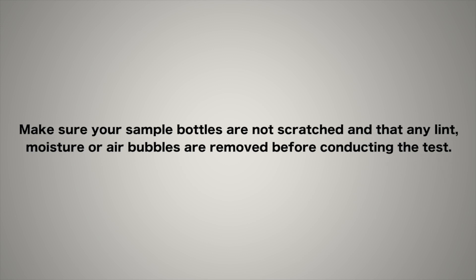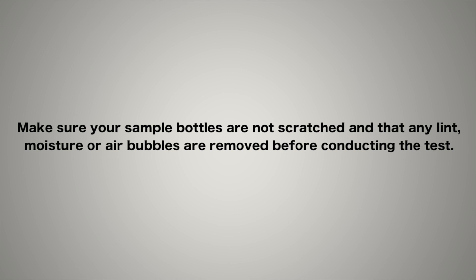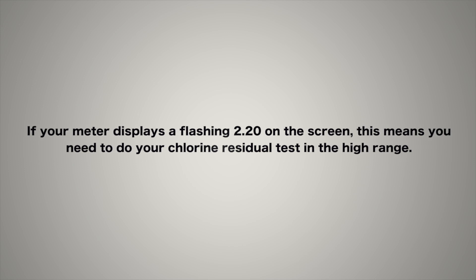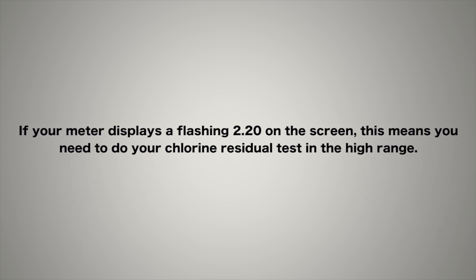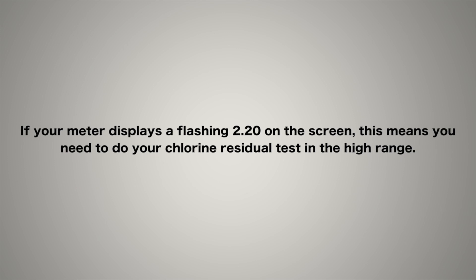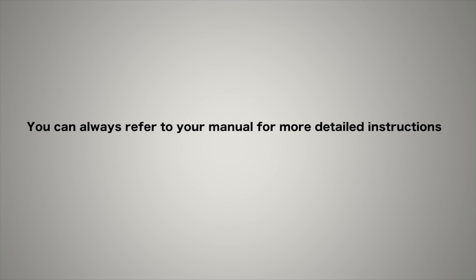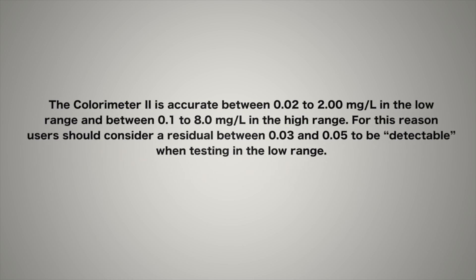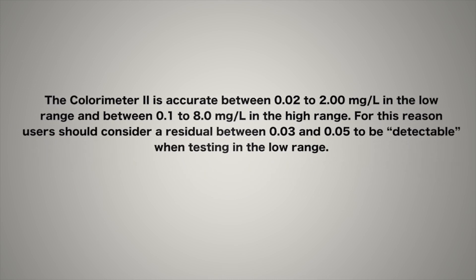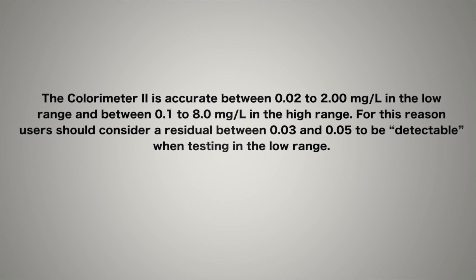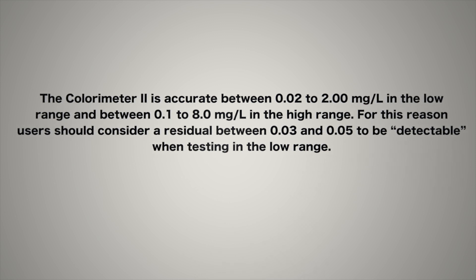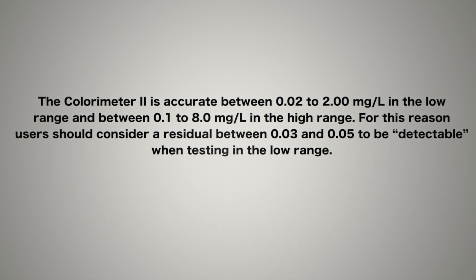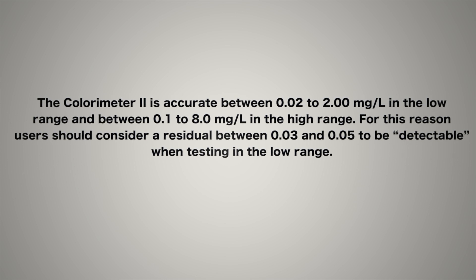For this reason, never use a colorimeter to test standing water for chlorine residual if not using the appropriate treatment for interference. If your meter displays a flashing 2.20 on the screen, this means you need to do your chlorine residual test in the high range. Refer to the instruction manual for specific details. You can always refer to your manual for more detailed instructions on how to conduct free and total residual tests in the low and high range. The kits will have an accuracy range. The Colorimeter 2 is accurate between 0.02 and 2.00 mg/L in the low range and between 0.1 and 8.0 mg/L in the high range. For this reason, users should consider a residual between 0.03 and 0.05 to be detectable when testing in the low range.